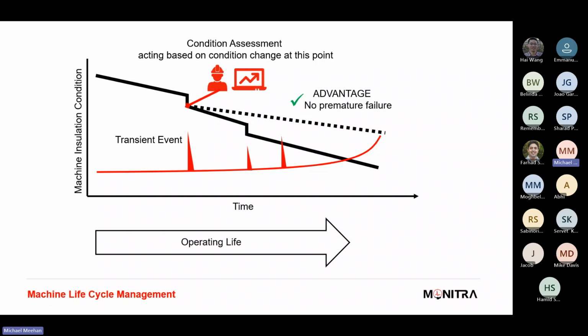PD, as we mentioned, can provide that online PD detection system where if there are any issues, and there's a multitude of potential issues that PD can detect. And then obviously there's the vibration analysis system, which is also one of the key features, if not one of the most critical features of the generating unit itself.